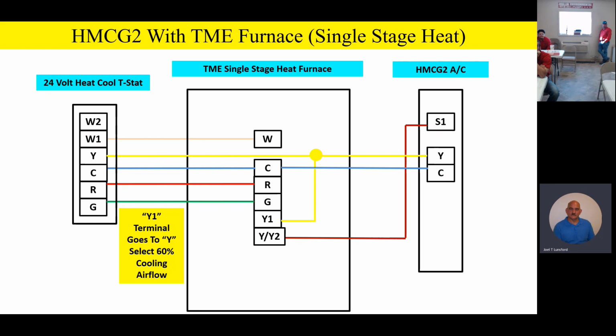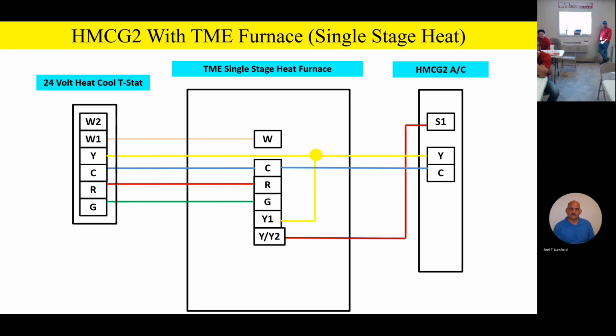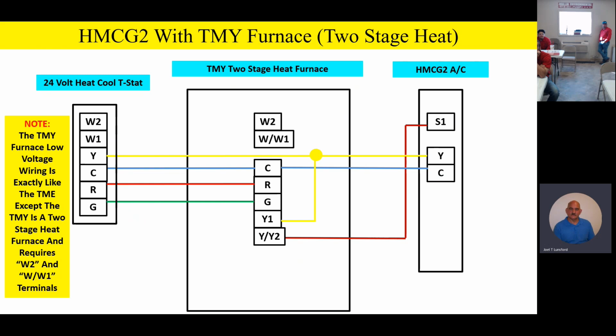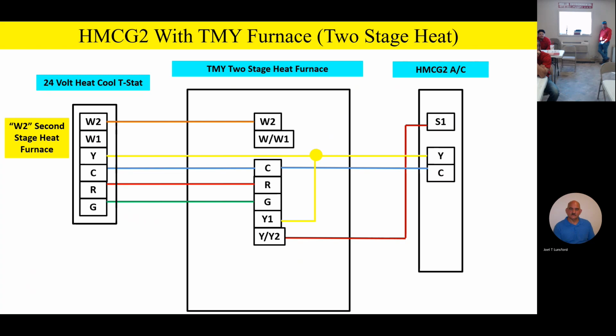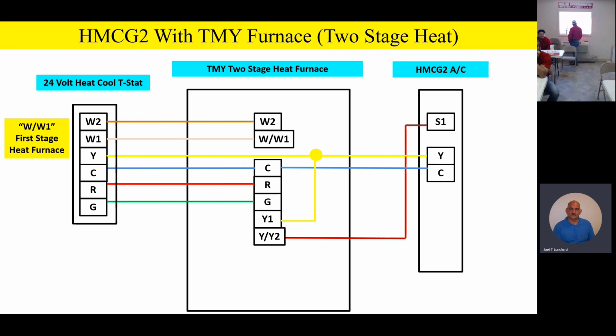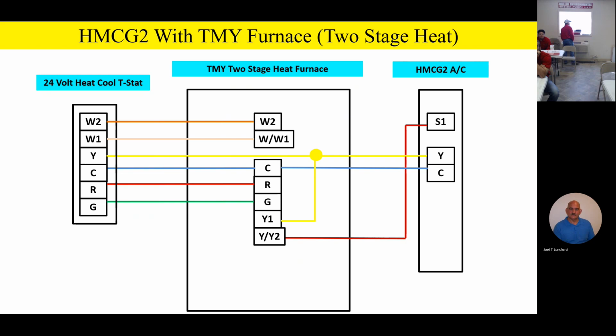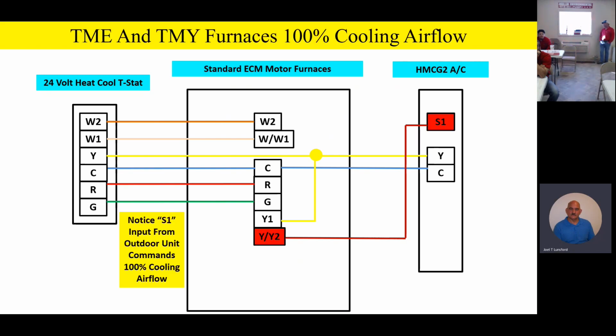And then when the outdoor unit says, hey, I'm at a higher capacity, it energizes... excuse me, I guess I showed the TMY furnace. It's the same thing. We got a little out of sequence there. So the TMY furnace is going to just have 2 stages of heat. Other than that, it's going to be wired exactly the same. But then when we go to the outdoor unit, we energize S1. Again, we're going to bring on our second stage cooling airflow.